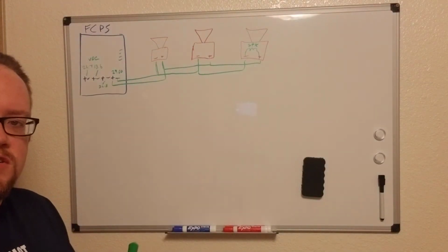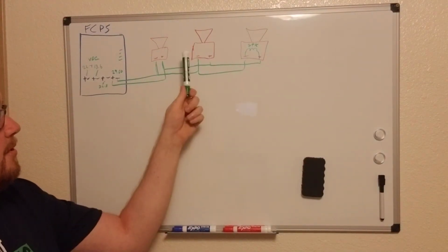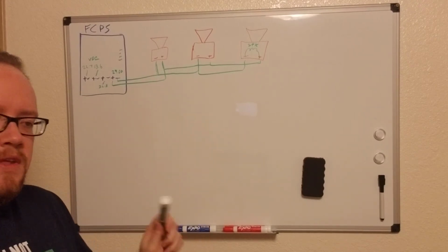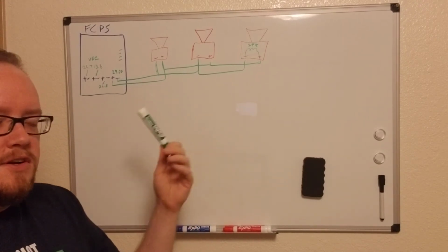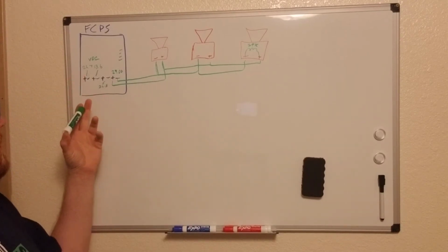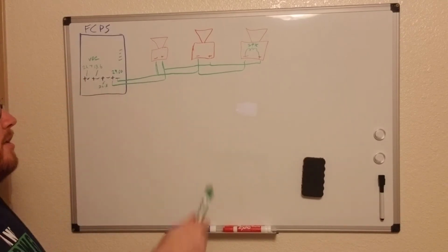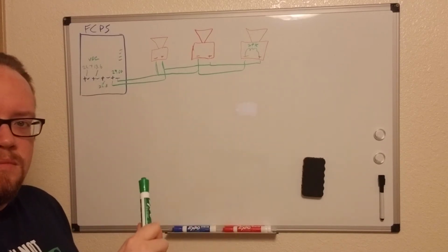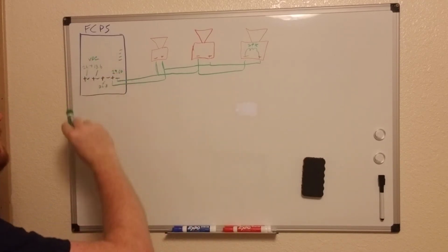you're trying to figure out which direction the wire runs, go out there, pull a horn strobe off the wall and check the voltage. You don't even have to pull the wires off. You can just meter it while it's still hooked up. And you see 26.7. Okay, well, this is circuit 1. You know this hallway is circuit number 1, or the NAC output of that power supply.